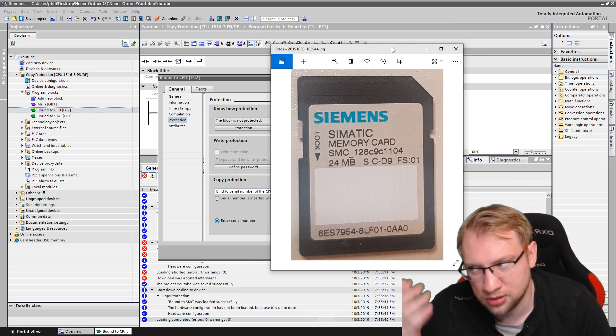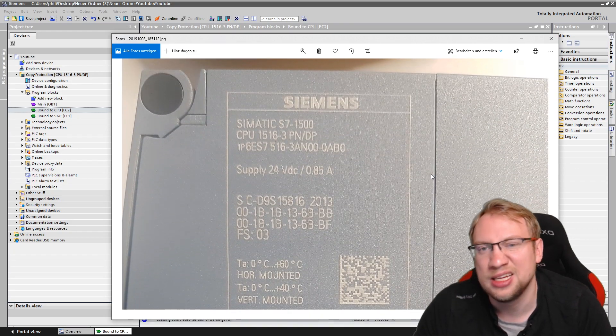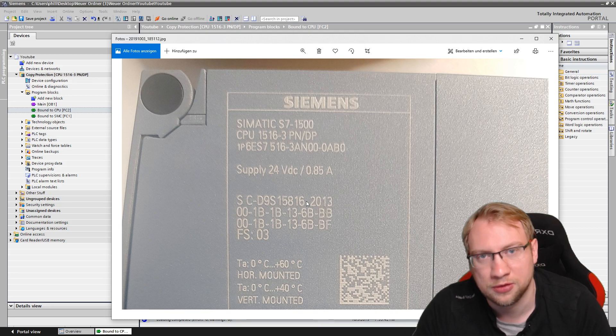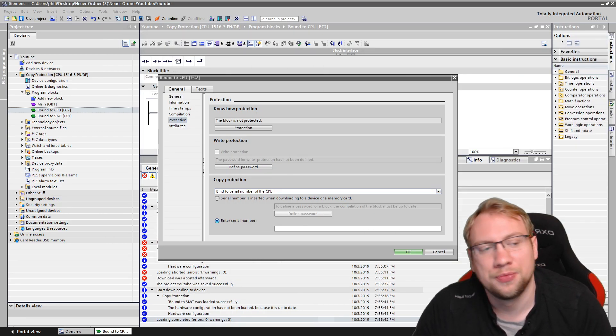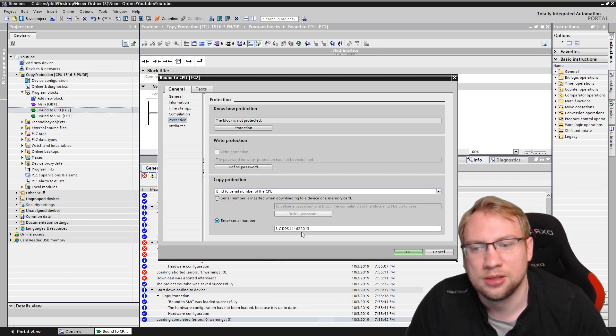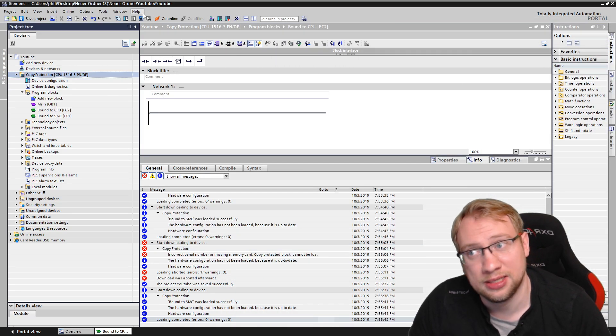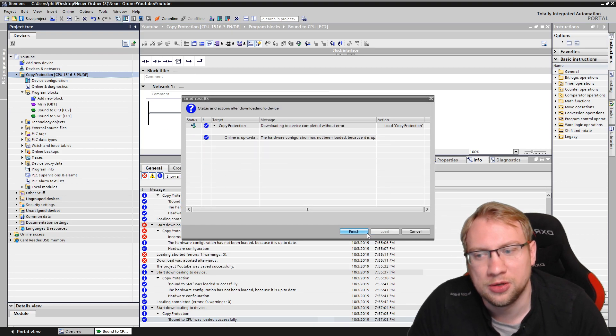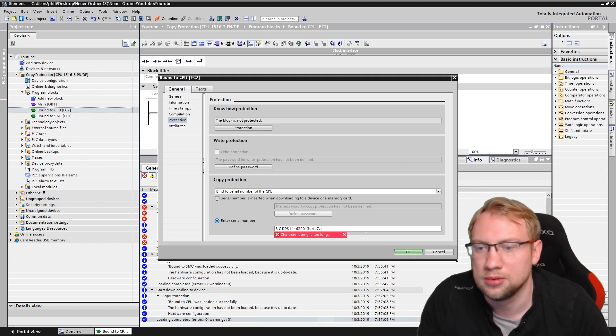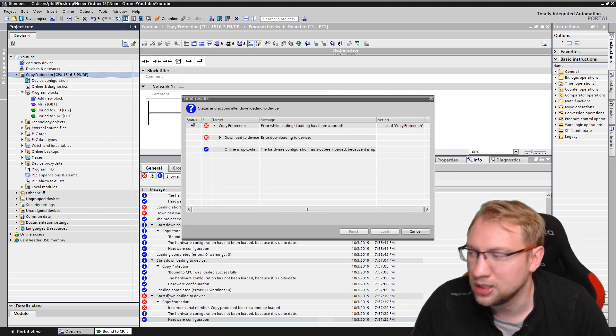For the CPU serial number, it's similar to the memory card. I have my PLC here — I took a picture — and on the side of the PLC you can see the serial number. In my case it's S-C-D9S2013. I copy and paste that serial number into the field, hit OK, and can download the program to this PLC with no problem because it's the correct number. If I enter an incorrect serial number, it says 'Copy protection — incorrect serial number' and I cannot download.